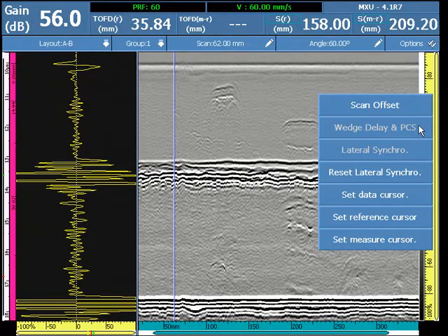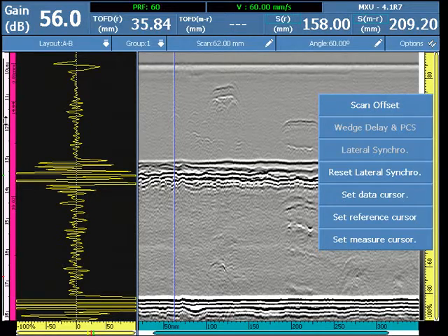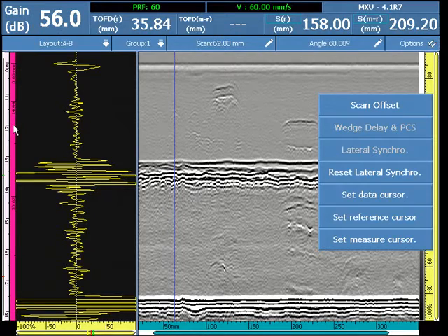The last calibration option will always be displayed here under a touch and hold or right click of the mouse. With that calibration, we can see that the ultrasound axis in microseconds is available and the TOFD axis in millimeters for the linearization of the A scan.